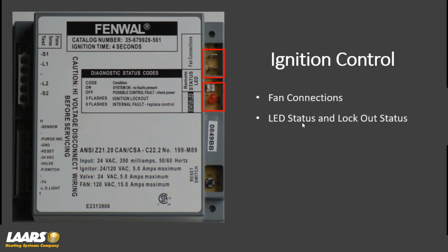Now, we also have LED status for your lockouts. There's an LED light on these ignition controls. This control is not the current control that we use. This was an image I had. I did not have a good image of the current control, so keep that in mind. But early example of this, 3 flashes is ignition lockout. So your LED light will give you a flash code 3 times. Okay, so you get that 3 flashes.